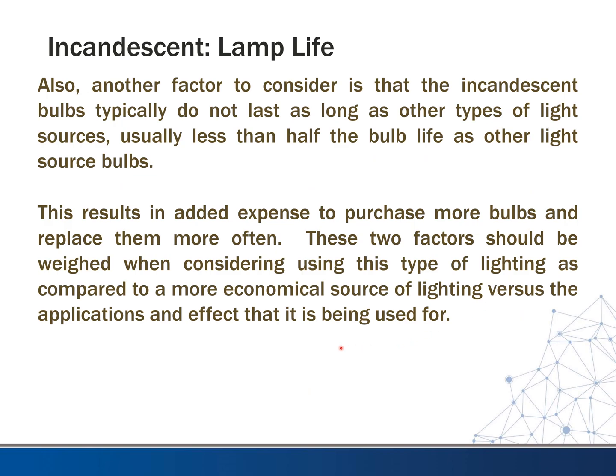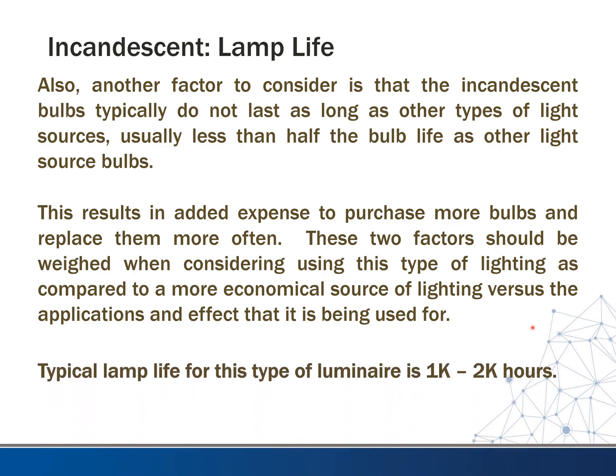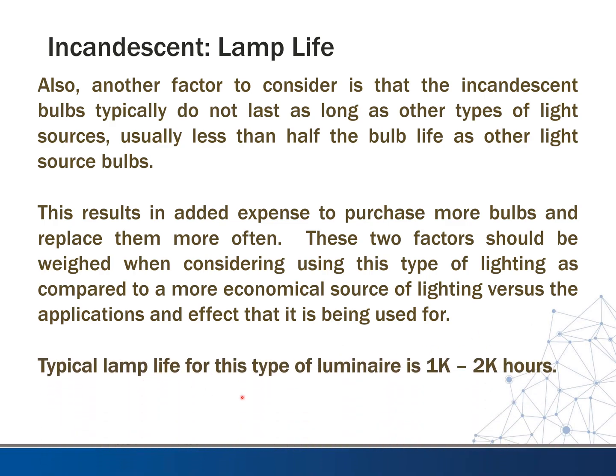Lamp life is another factor to consider. Incandescent bulbs typically do not last as long as other types of light sources — usually less than half the bulb life of other sources. This results in added expense to purchase and replace bulbs more often. These two factors should be weighed when considering this type of lighting versus more economical sources. Typical lamp life for this luminaire is generally considered to be in the one to two thousand hour range.